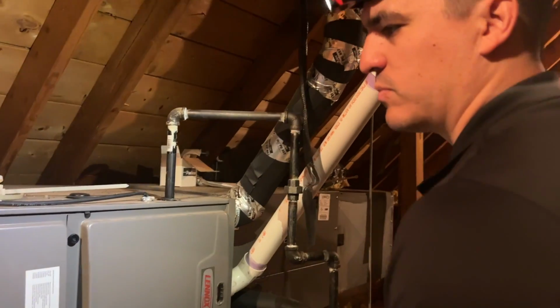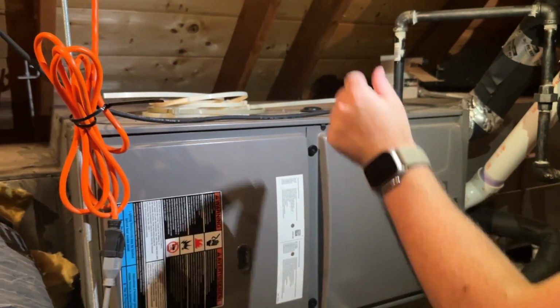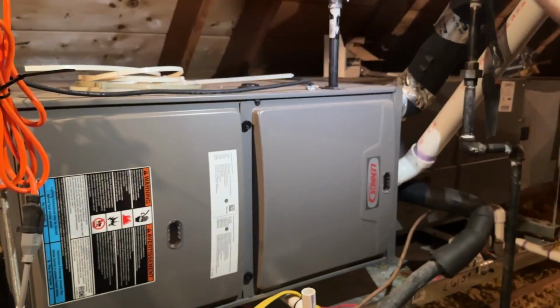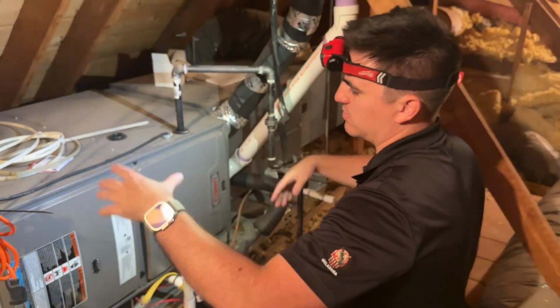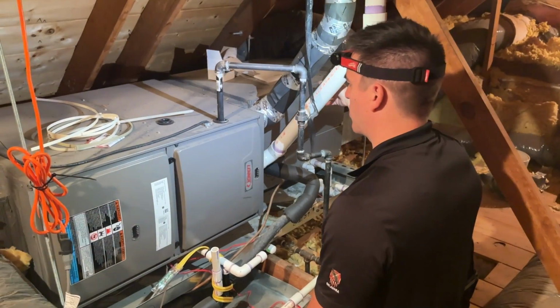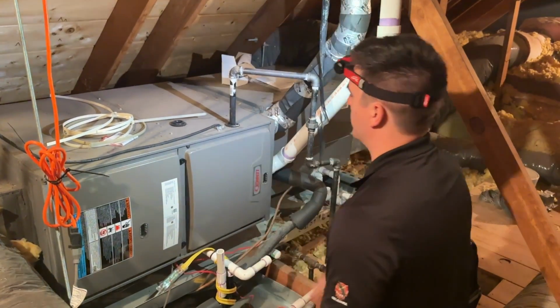There's some units where you'll go in the attic and it's connected via plumber strap, which is the small metal straps with the holes in them going up, rectangle strap. And over time, that weight difference, and if it's not level when the straps are screwed in, it can cause some bowing. It makes it difficult to get the doors off, which can be a problem.